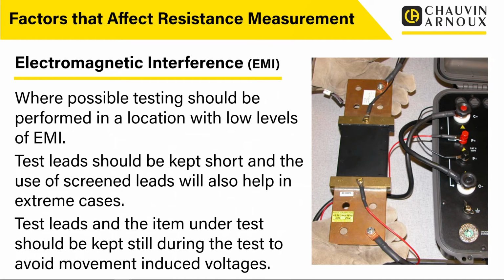Test leads should be kept short, because long test leads and big loops of test leads act like an antenna, and they will attract these induced voltages and currents more. The use of screened leads will also help in extreme cases. If there's nothing else we can do, we could use screened cables, and that will minimize these effects. Test leads and the item under test should be kept still during the test to avoid movement-induced voltages. So position everything where we can and try not to move it during the testing, and that will also help to avoid electromagnetic interference.